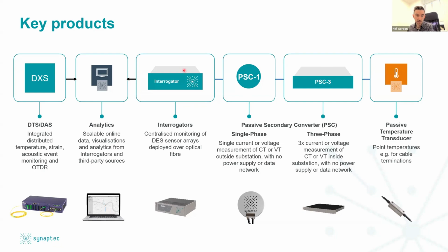Beyond the sensors, then, we have the interrogators, which monitor centrally all of the sensor arrays over optical fiber, and they generate measurement data, typically in IEC 61850 sample values, and they perform rapid onboard functions, for instance, 87L protection, differential protection algorithms, to enable those protection scheme enhancements that Sol will take you through. Now, these interrogators, I should say as well, are also type tested to the same level of rigor as a protection relay or another equivalent IED in the substation. So they've been through a rigorous amount of testing for that environment.